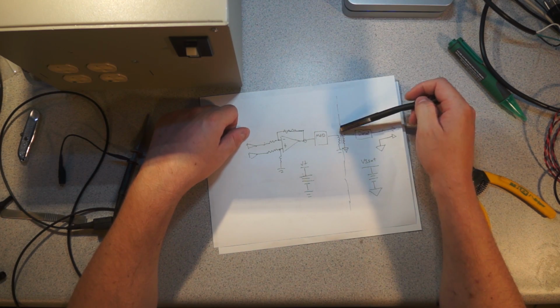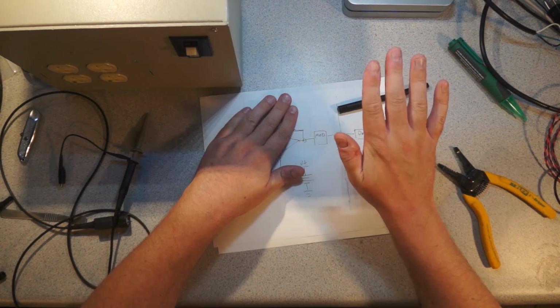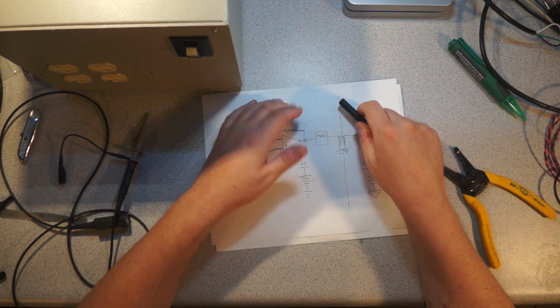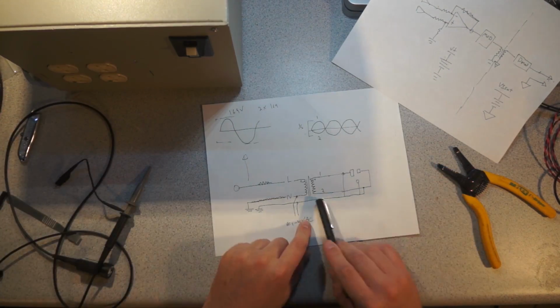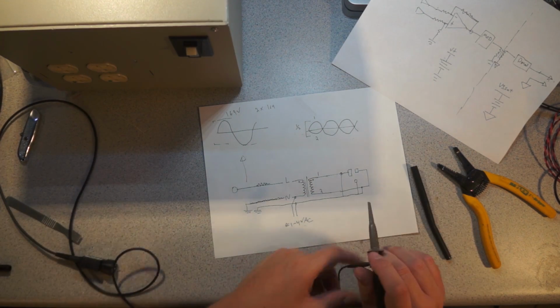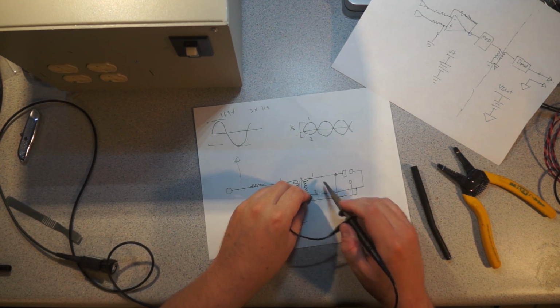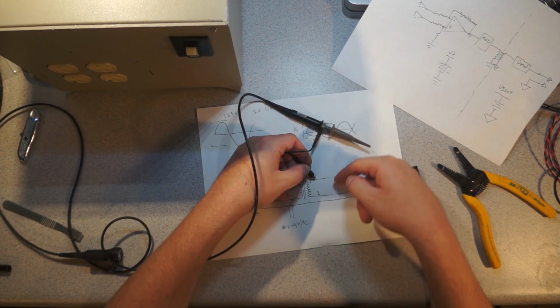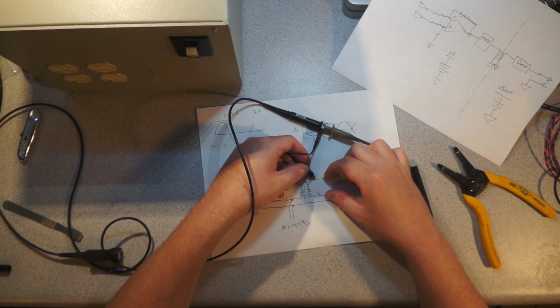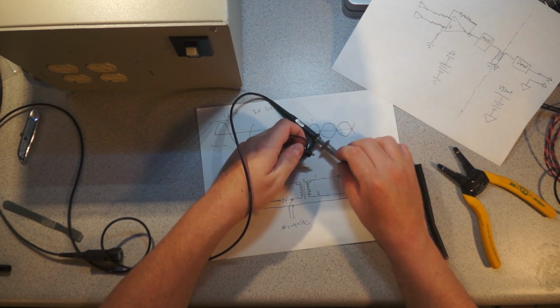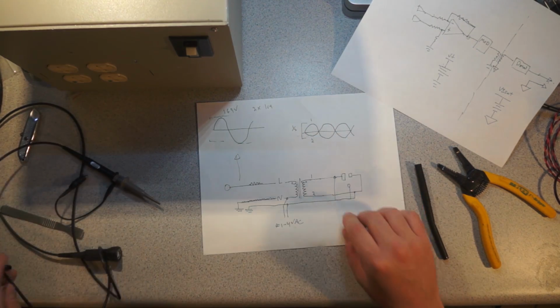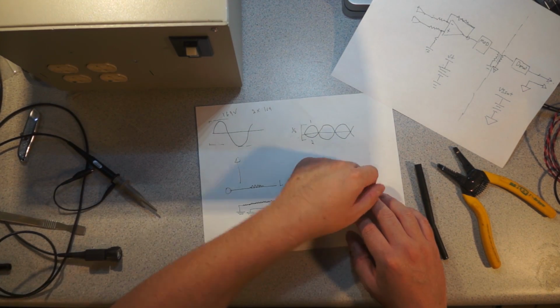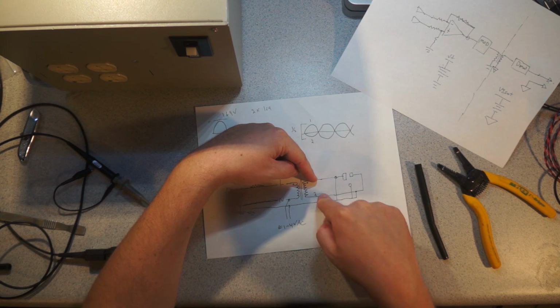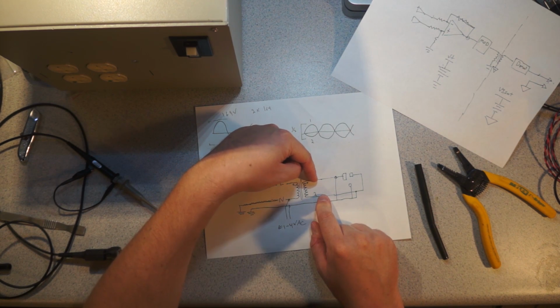The advantage of a dedicated purpose isolated differential probe like this is that you can probe two different sections of the circuit at two different voltages simultaneously. Whereas with something like this, if you want to probe line 2 you connect your probe up here, and then you're like, oh, I've got to look at line 1 too, and you connect another probe over here, it'll short through the two ground leads. That's pretty simple, and I'd hope most people wouldn't think about doing something like that, because obviously if you're connecting your grounds to both terminals, something's going to go wrong.